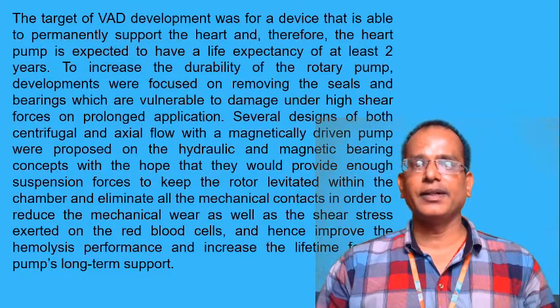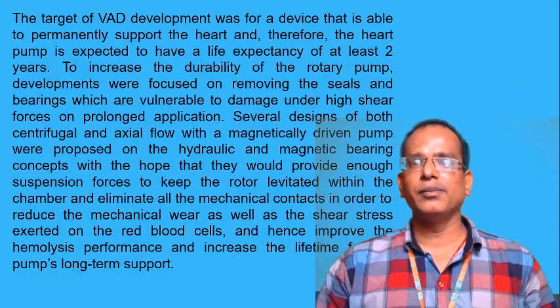Third generation VAD development was for a device able to permanently support the heart, and therefore the pump is expected to have a life expectancy of at least 2 years, which increases the durability of a rotary pump. They also focused on removing the seals and bearings, which are vulnerable to damage under high forces on prolonged application.